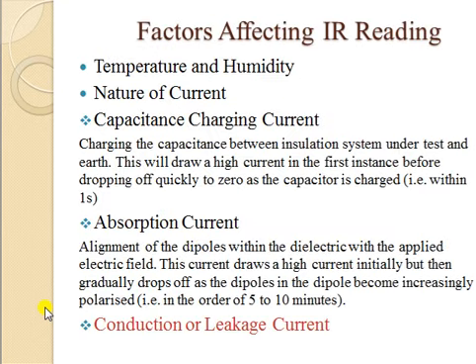When you are doing insulation resistance testing, what may be the different factors affecting the insulation resistance reading? The first two factors are always temperature and humidity — these are typically environmental factors. Depending upon the amount of temperature or humidity present in the environment, your insulation resistance value will change. These are the two main factors affecting insulation resistance readings.